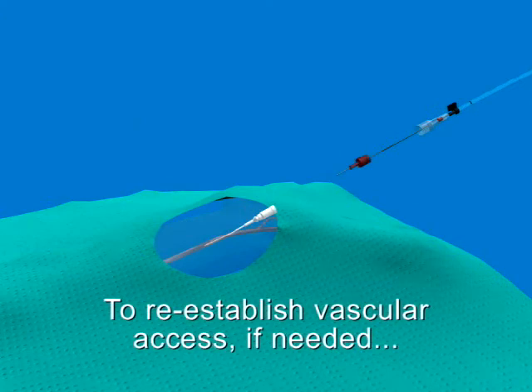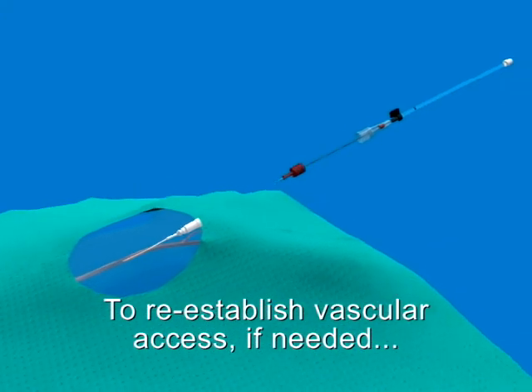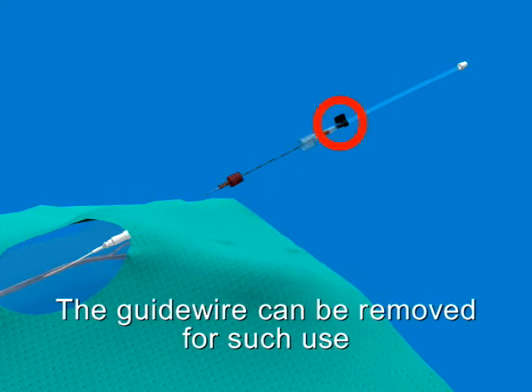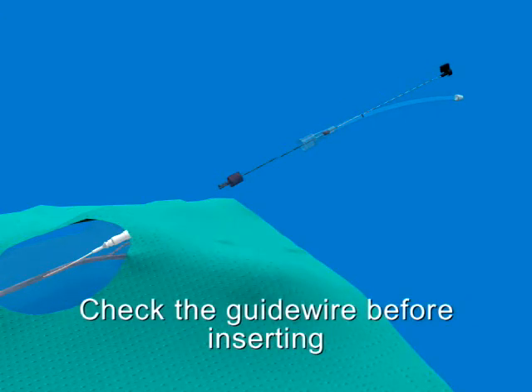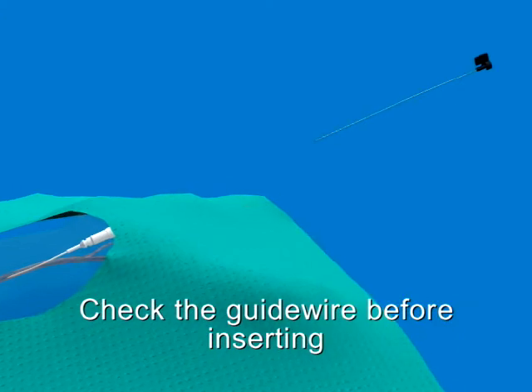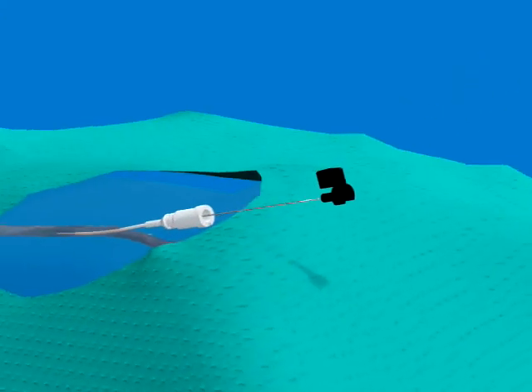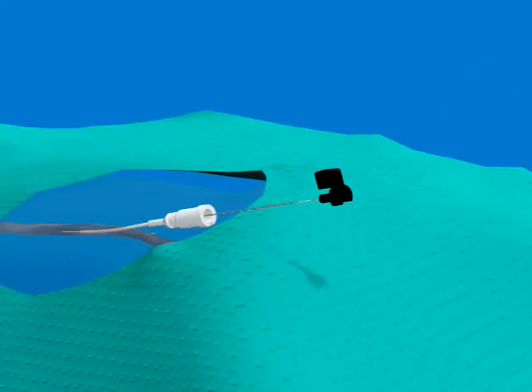This product is designed so the integral guide wire can be removed from the needle and feed tube by pulling up on the wire handle. Withdraw the wire gently to avoid blood splatter. Examine the wire for any damage after pulling back through the needle. If the wire is frayed, a new wire or new device must be used.